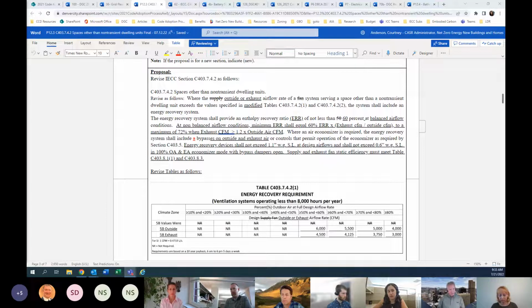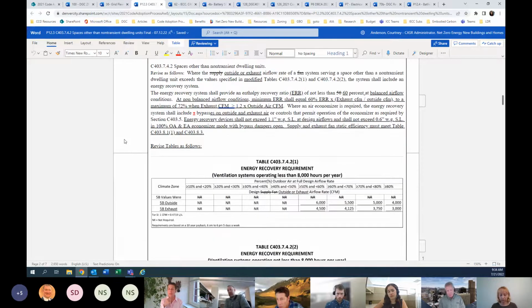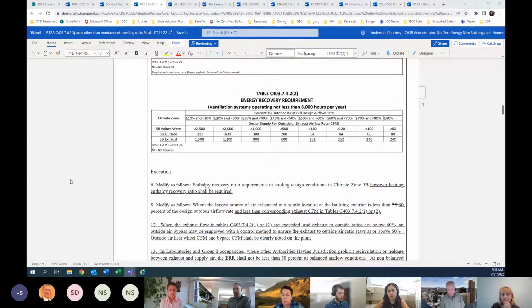If I choose to use a DOAS system for that same building, now I've got a system that, first of all, probably runs more than 8,000 hours, and now that system has essentially 100% outside air. So it gets interesting in how you choose to do things. If I was directed by an owner to loophole this, first of all, let me say that it's very much harder to loophole this in Denver than anywhere else, primarily because of exception 8, and has been in the last rounds too. Even in a real building, not a PTAC building, that you look at and say that should have energy recovery, all you had to do is provide more than one exhaust fan, right? And you met exception 8. So thank you, if this is what we're trying to do, and we are, that really covers it.